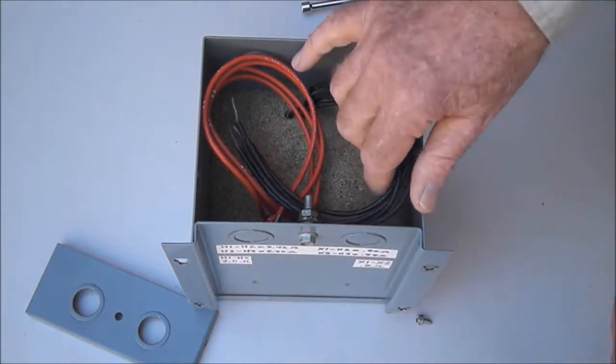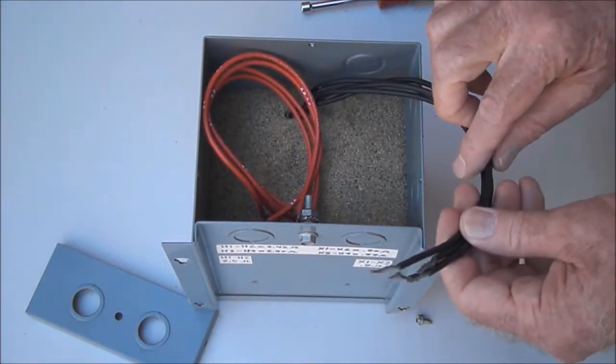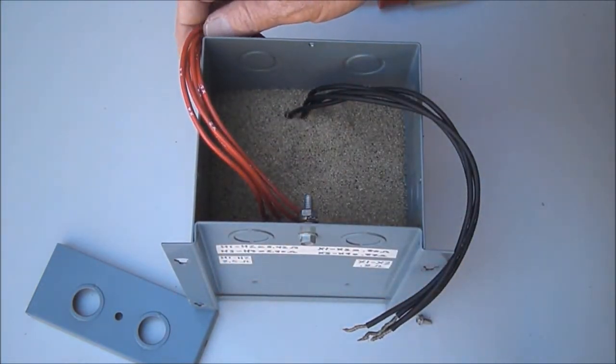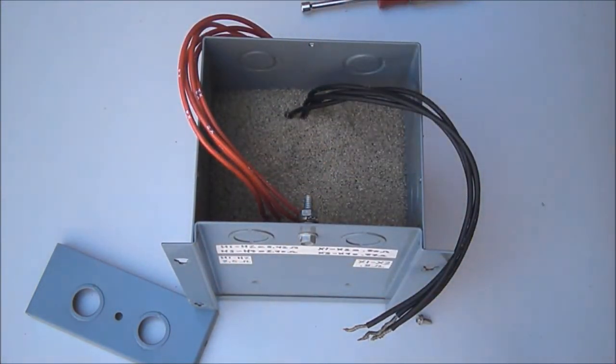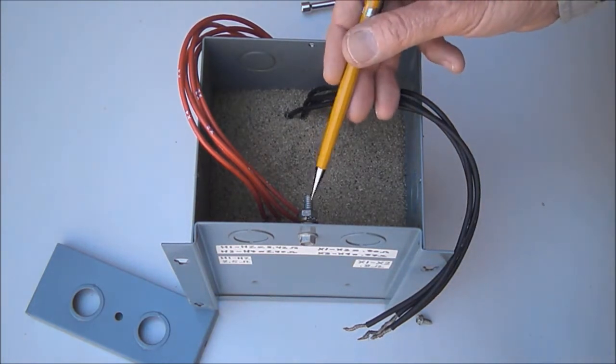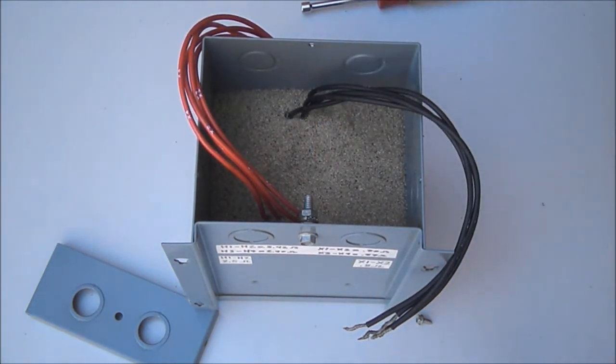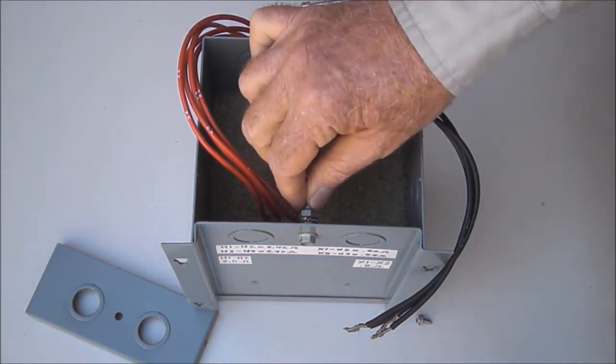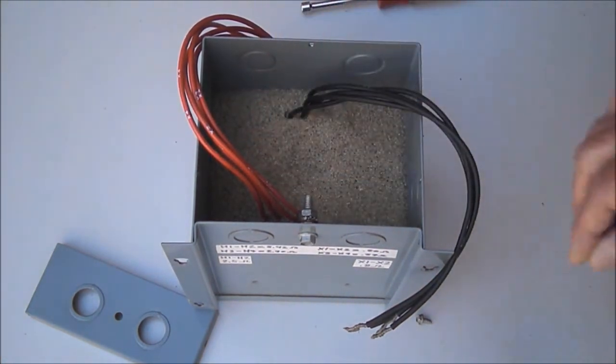Inside we see primary wires that are black and secondary wires that are red on this particular type of transformer, including a quarter twenty bolt for grounding which would be connected to the grounding electrode or grounding wire of the system it's connected into.